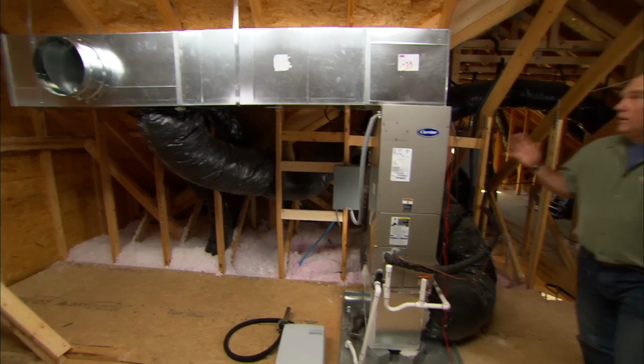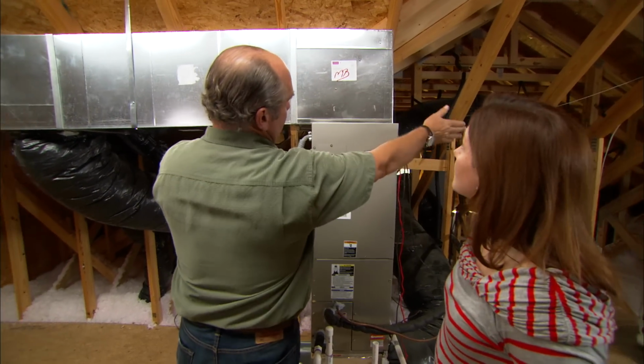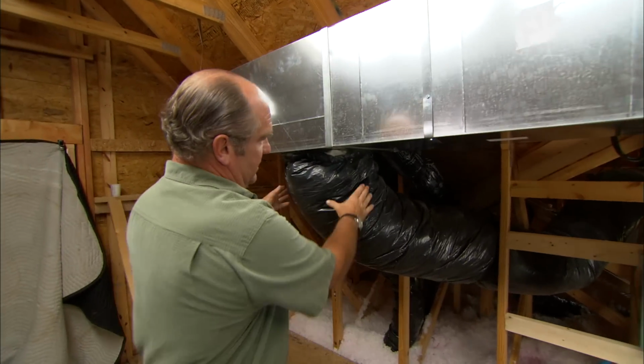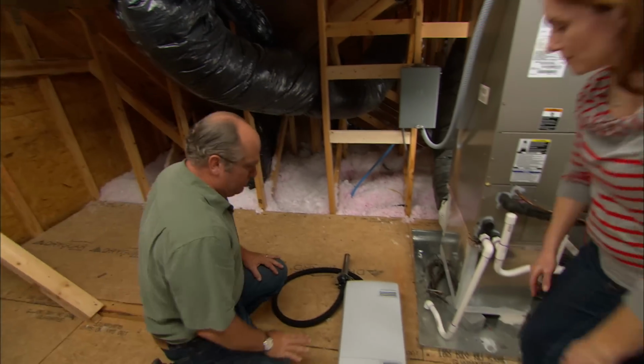All right, Cindy, we've made a lot of progress up here. Remember, your ductwork used to come off the top and went both ways. Right. Now we come in one direction here, nice solid trunk. You can see the flexible connections are made. And this is your new whole house humidifier right here.